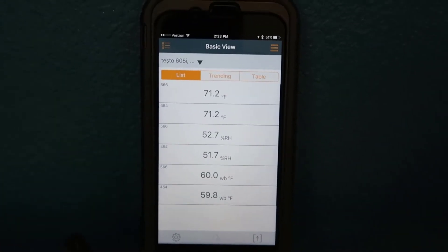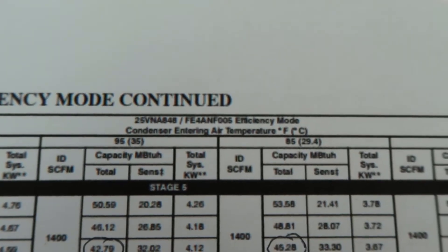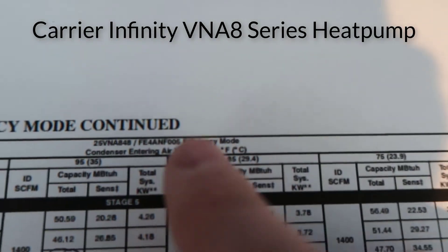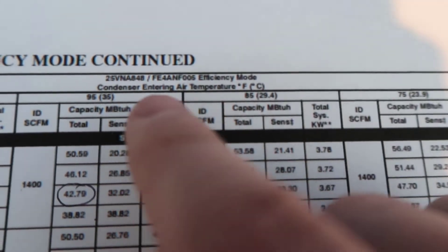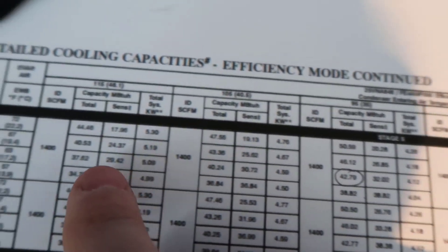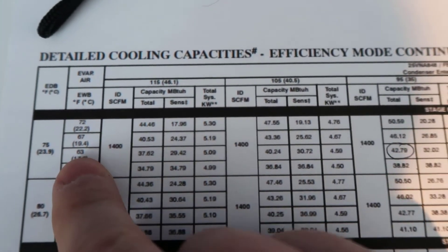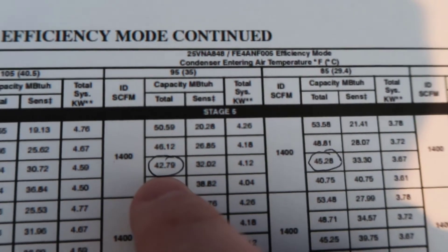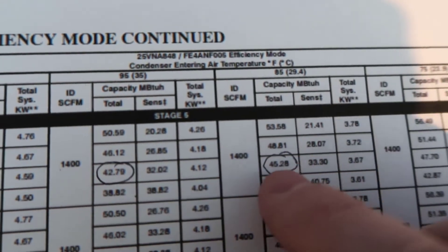Before we make our reading, we want to know what the system should be reading. I've pulled up my detailed cooling capacities for my particular system — a 25VNA848 condenser with an FE4ANF005 air handler. I'm going to be in between the capacities for 85°F and 95°F outdoor dry bulb, at max high stage, with indoor conditions close to 63°F wet bulb and 75°F dry bulb. So we're looking for between 42,790 and 45,280 BTUs.